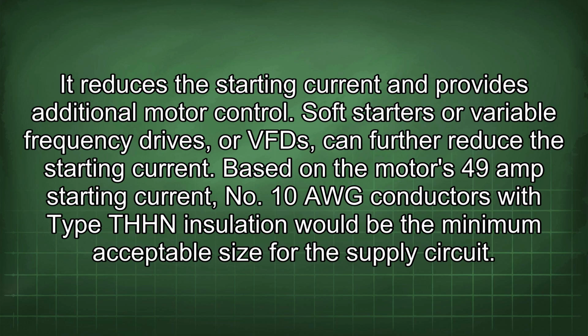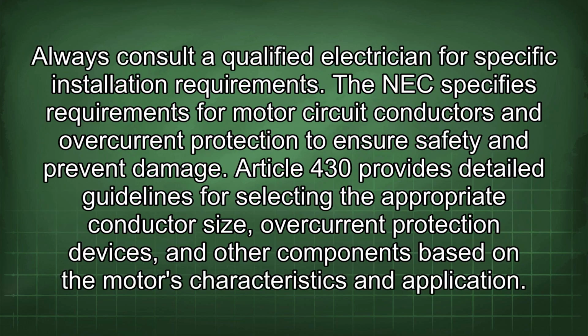Based on the motor's 49 amp starting current, 10 AWG conductors with type THHN insulation would be the minimum acceptable size for the supply circuit. Always consult a qualified electrician for specific installation requirements. The NEC specifies requirements for motor circuit conductors and overcurrent protection to ensure safety and prevent damage.